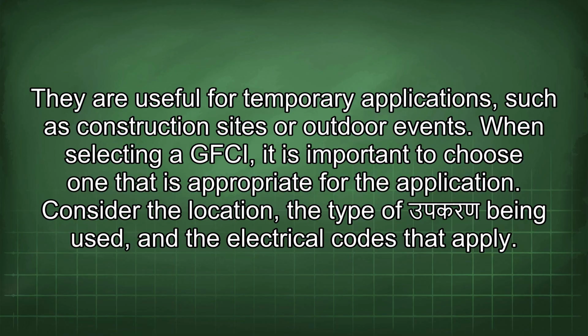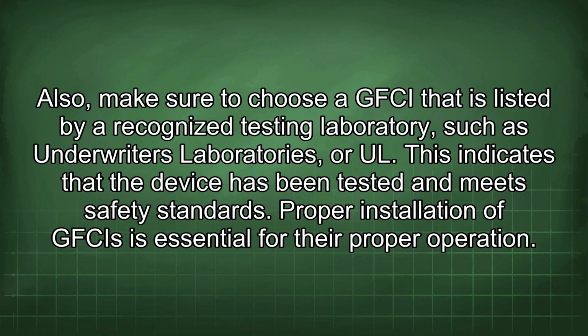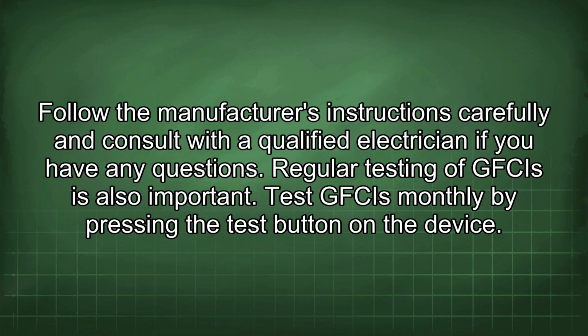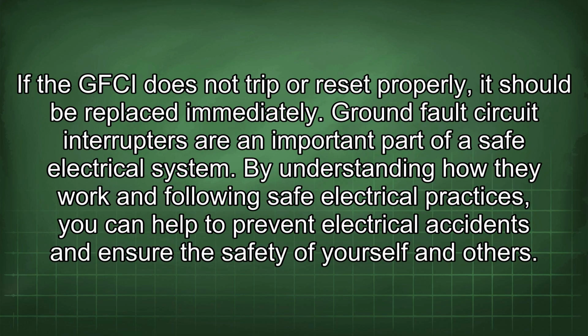When selecting a GFCI, it is important to choose one that is appropriate for the application. Consider the location, the type of appliance being used, and the electrical codes that apply. Also, make sure to choose a GFCI that is listed by a recognized testing laboratory such as Underwriters Laboratories or UL. This indicates that the device has been tested and meets safety standards. Proper installation of GFCIs is essential for their proper operation. Follow the manufacturer's instructions carefully and consult with a qualified electrician if you have any questions. Regular testing of GFCIs is also important. Test GFCIs monthly by pressing the test button on the device. If the GFCI does not trip or reset properly, it should be replaced immediately.